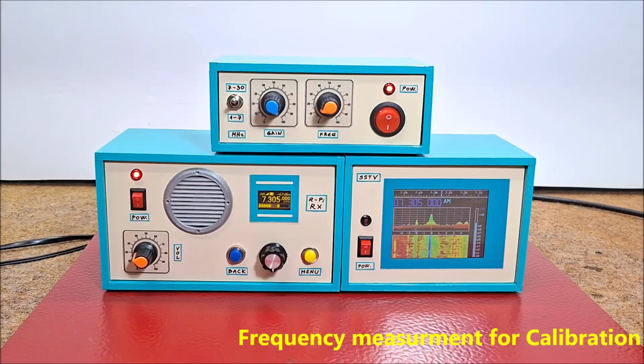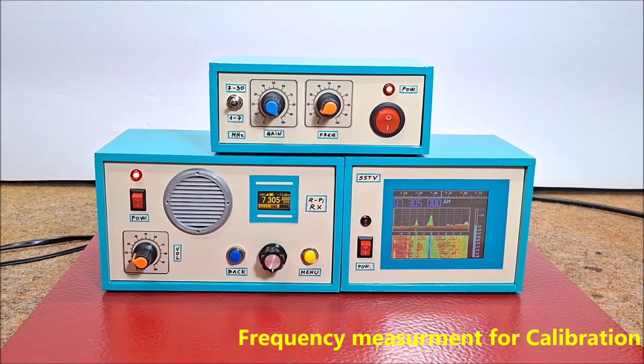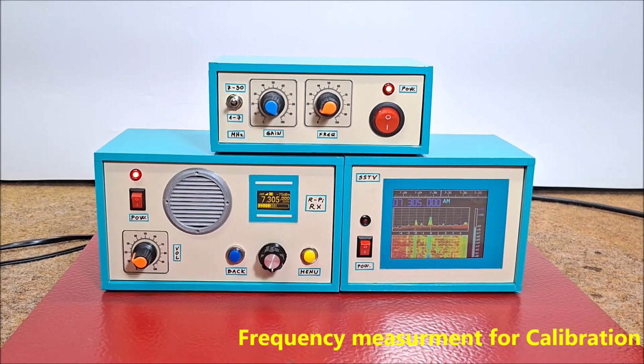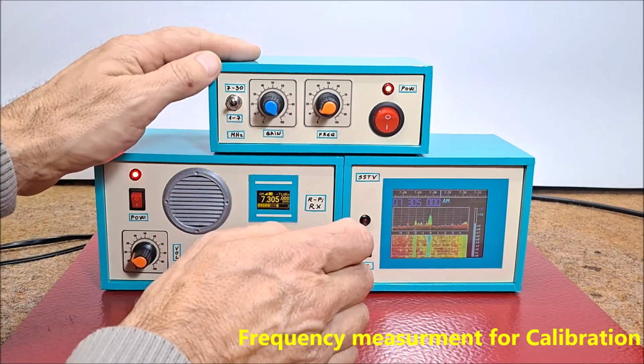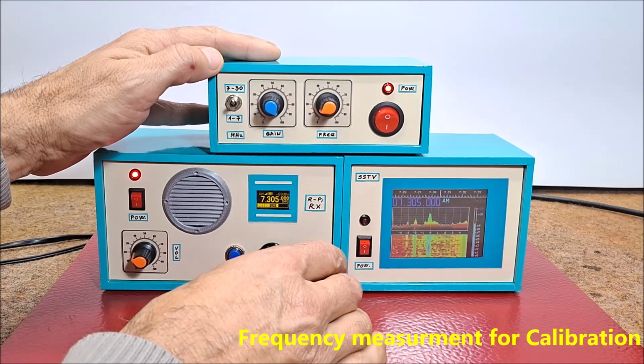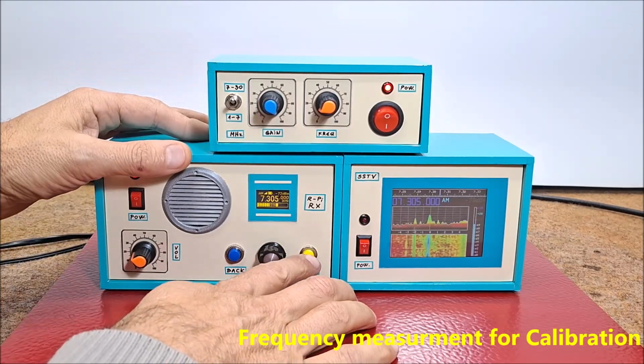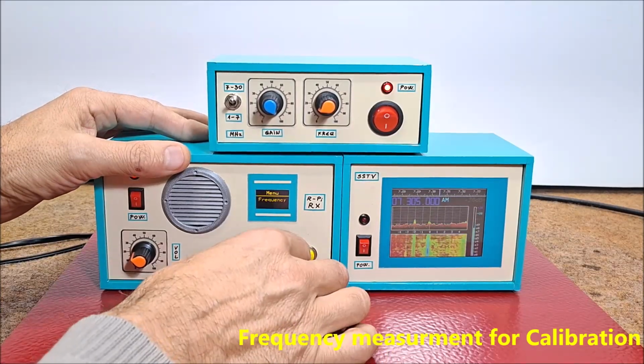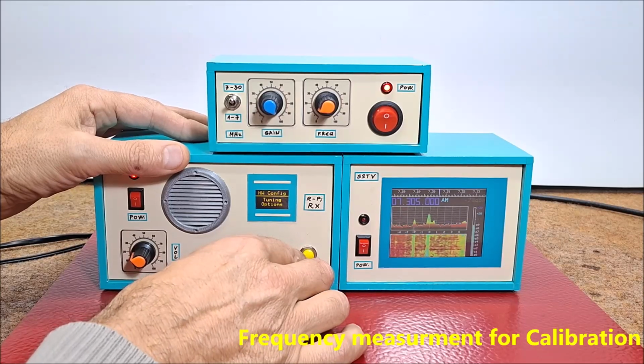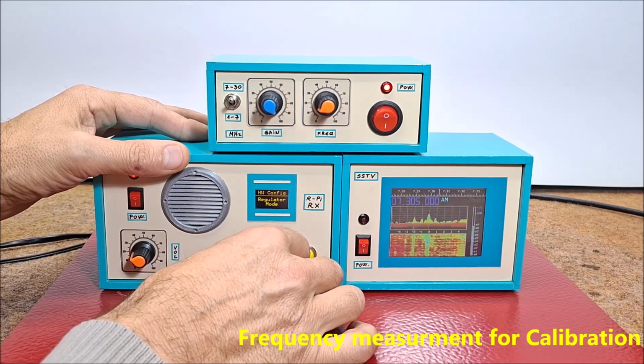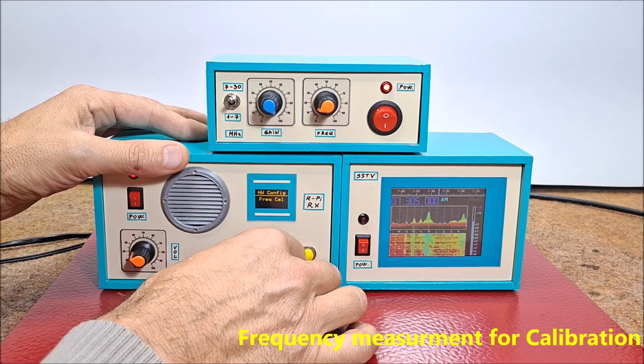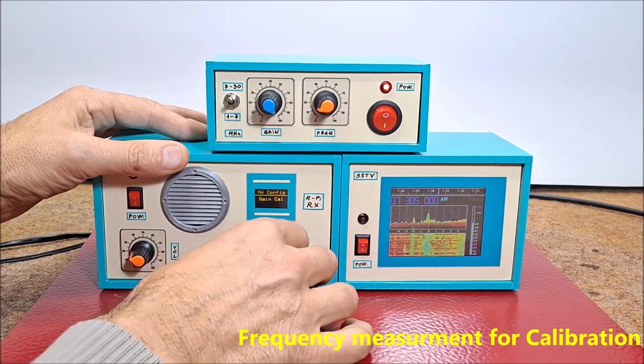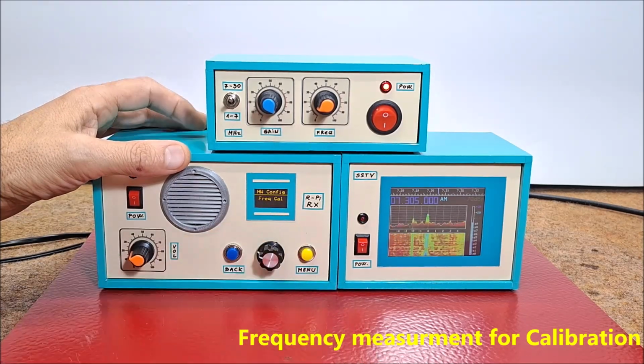The latest software introduces a frequency measurement feature that can make the calibration process easier. The receiver can be calibrated by tuning to an AM station with a known carrier frequency. Let's find this option. So we have gain calibration and frequency calibration.